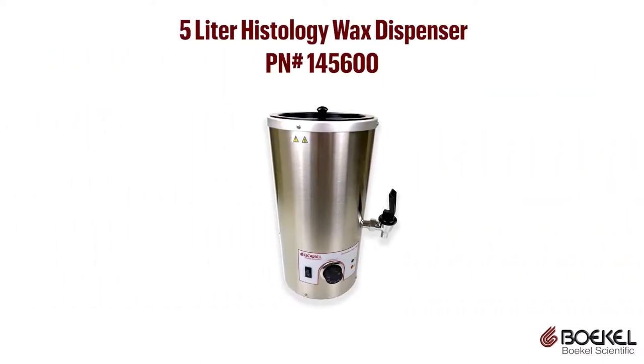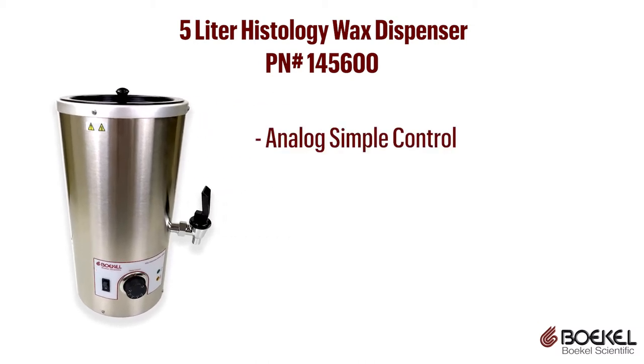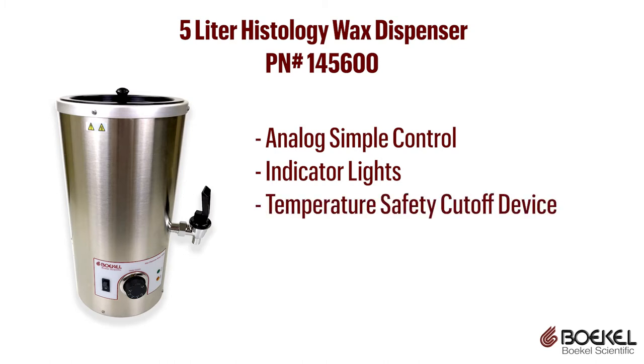For embedding, Boekel Scientific has the 5-liter histology wax dispenser. The 5-liter wax dispenser has analog simple control, indicator lights, and a temperature safety cutoff device.